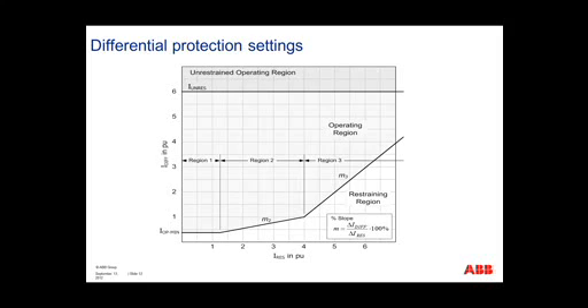Most microprocessor relays have 3, 4, or 5 regions that you can set. Here we are showing 3 regions, M2 being a slight slope, and M3 having a greater slope, giving you more security through either CT saturation or errors in your calculations. That's why you would see a higher slope here at M3, typically for CT saturation.